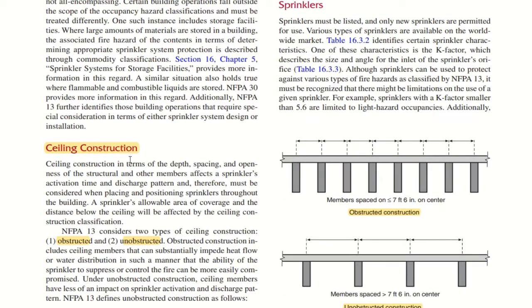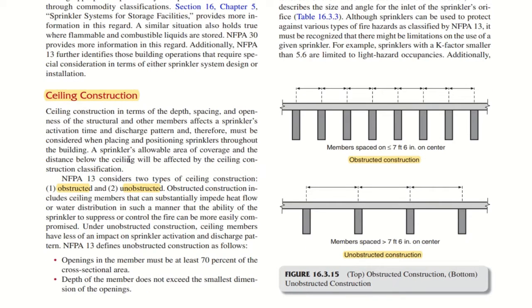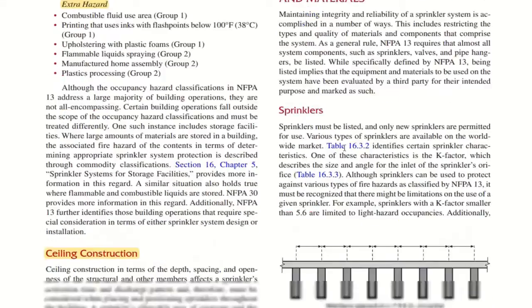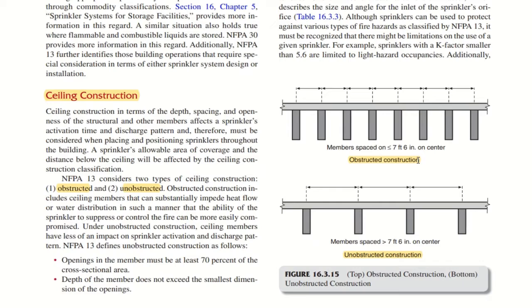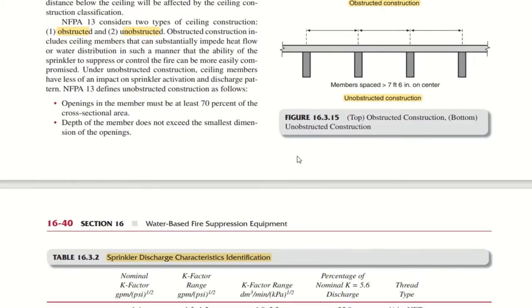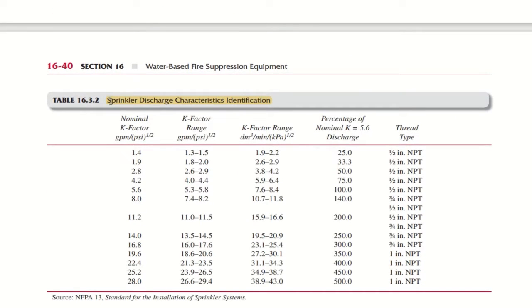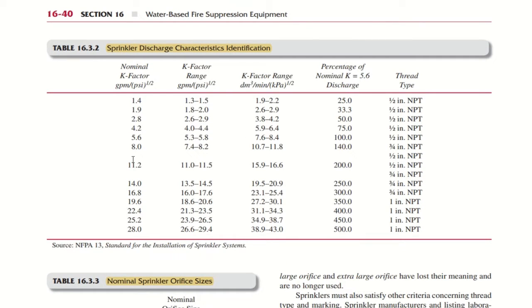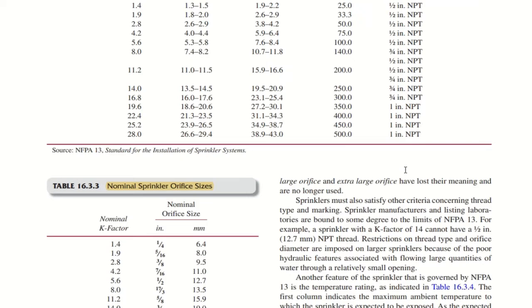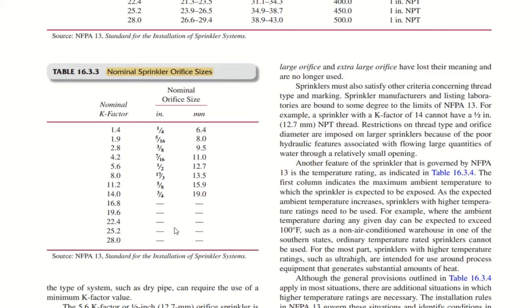So ceiling construction: there are two types of ceiling construction that NFPA 13 considers. One is obstructed ceiling construction, and the other is unobstructed ceiling construction. Here they have just shown the obstructed construction, and here you have unobstructed construction. Here you have one more table, sprinkler discharge characteristics identification. Here you have the nominal K factor, the percentage of discharge, and the thread, which is already covered in our earlier slides. So this is an important table.